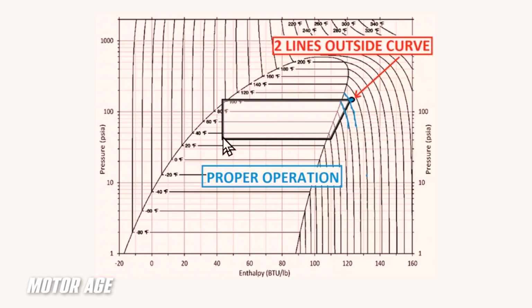What can be seen here as a normal characteristic is the temperature at which we come across the evaporator. We can see it is just above freezing, which is desirable for yielding us those cool cabin temperatures. We have a little bit of superheating take place, which is what we need to prevent liquid refrigerant from slugging the compressor, if you recall from earlier in the video. And these temperature lines we have here, I have highlighted in blue, showing the two temperature lines to the right of the chart. Typically, you will see this point here, our high side pressure, stay darn close to this, indicating a little bit of superheat, but not too much. This is what we call desirable and expected proper operation of a refrigerant loop.